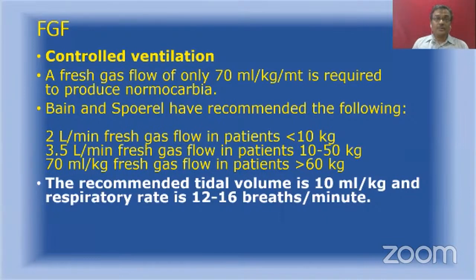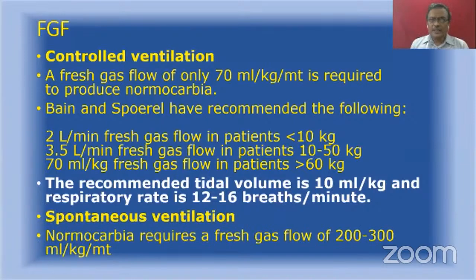If you want to eliminate carbon dioxide, rather than increasing the rate too much, you go on increasing the fresh gas flow to the Bain circuit. That is more effective than doing too much hyperventilation with a Bain circuit. Now, spontaneous ventilation is not recommended for a Bain circuit for a long time. But when you use Bain circuit for spontaneous ventilation, you need to use a very high gas flow of around 200 to 300 ml per kilogram per minute, which comes to about 2 to 3 times the minute ventilation. So that's a very important point when you use Bain circuit during your extubation process. Whenever you use it, always go for a higher flow. Otherwise, there will be carbon dioxide accumulation and the hypercarbia itself can lead on to delayed recovery.